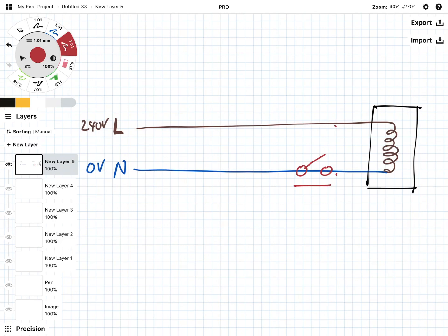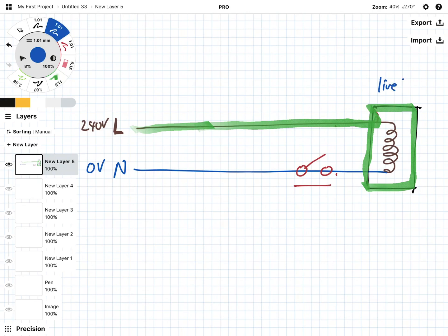So what's the actual reason? Let's say if you switch off but there's damaged insulation. The live wire, there's a frayed wire and it touches the metal casing. If you look at this path here, this is 240V all the way until here. The whole casing is actually 240 volt, live at 240 volt.